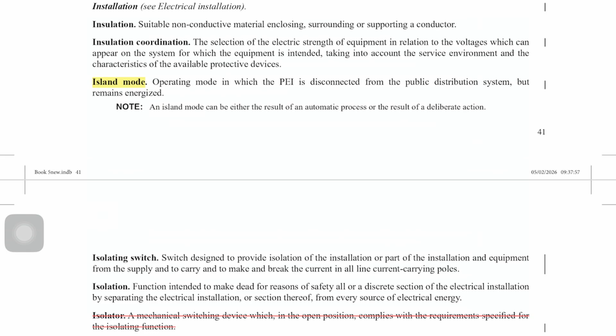Here's the one that comes up quite a lot for prosumer installations. You've got island mode. So PEI stands for prosumer's electrical installation. I've kept this in here, but when we were working on the regs, because things got changed at the last minute, and when we were doing the final proofing, we decided we really wanted to do away with the word isolator. All right, there isn't a thing called an isolator. It's a switch disconnector, switch, and this is all about turning off on load or off load.